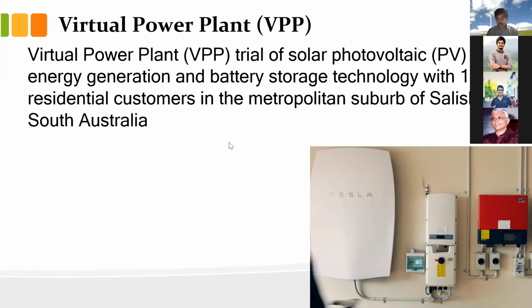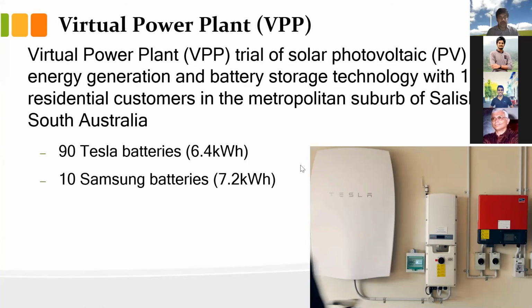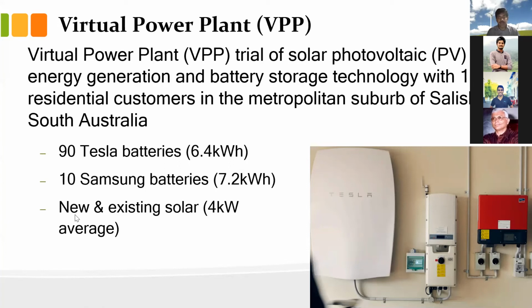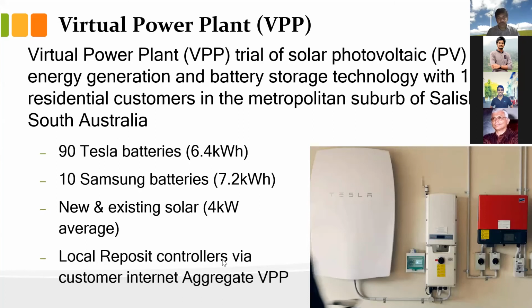This power plant, this is one of the houses, has 90 Tesla batteries, each 6.4 kilowatt hour, 10 Samsung batteries, new and existing solar, solar inverters, and Local Reposit controllers where the customer internet aggregates into the VPP, the virtual power plant. So this is one way: you will have visibility of these 100 customers collectively, not individually. That's good enough, because the system operator doesn't need to know what's happening individually.